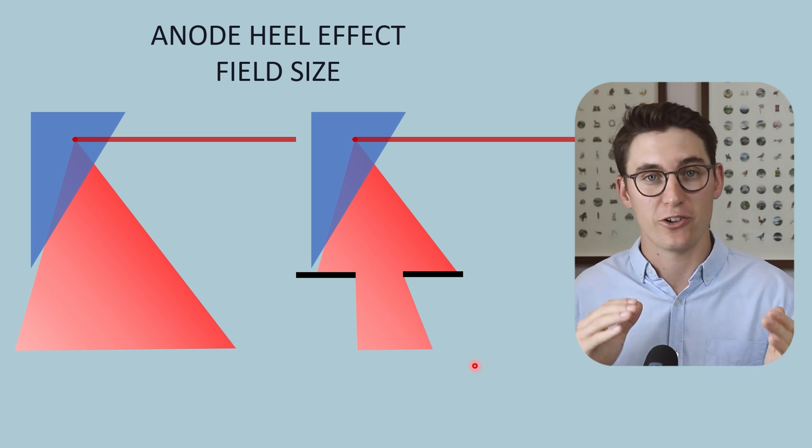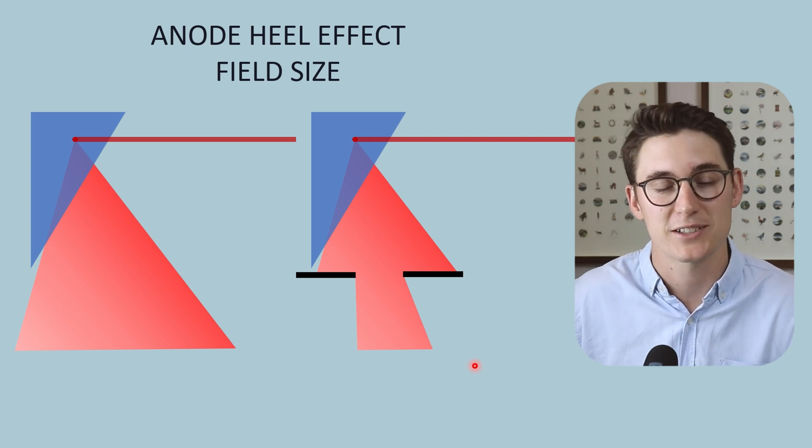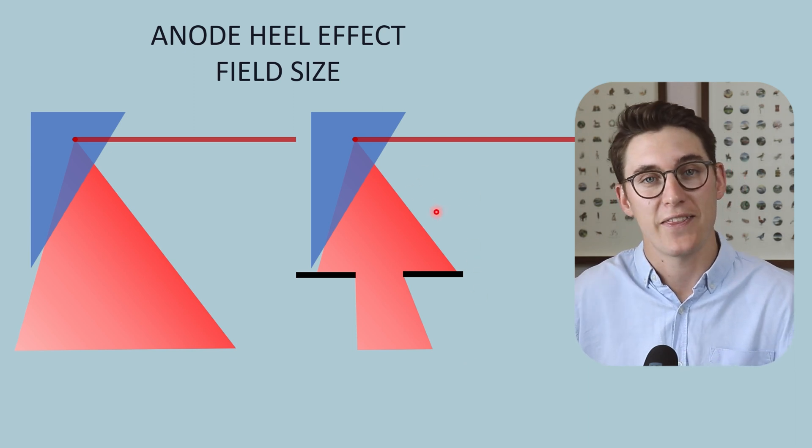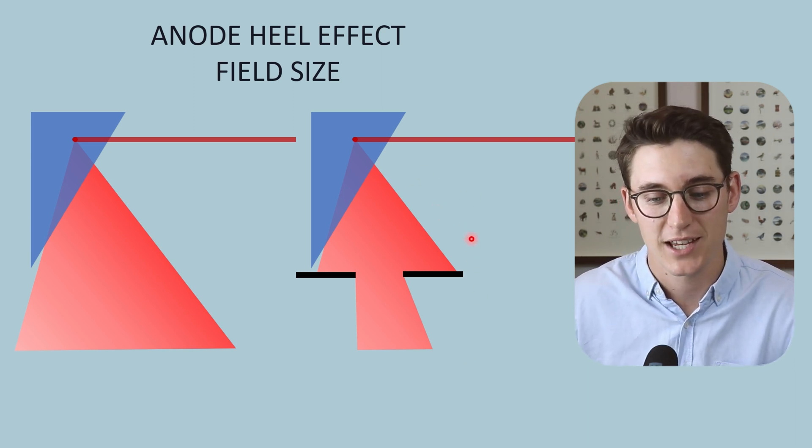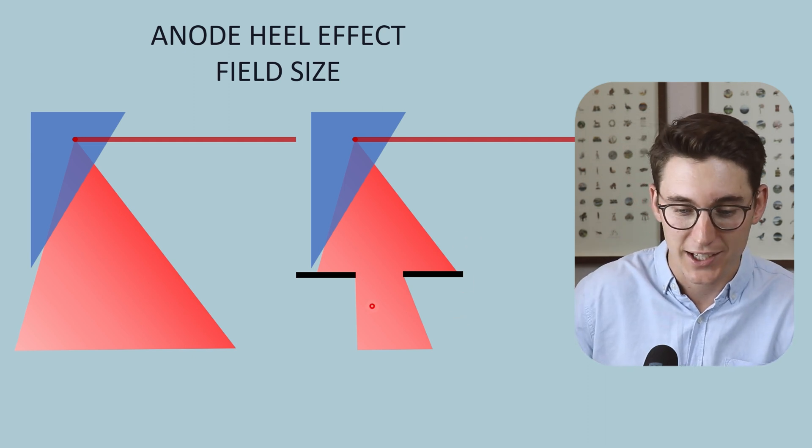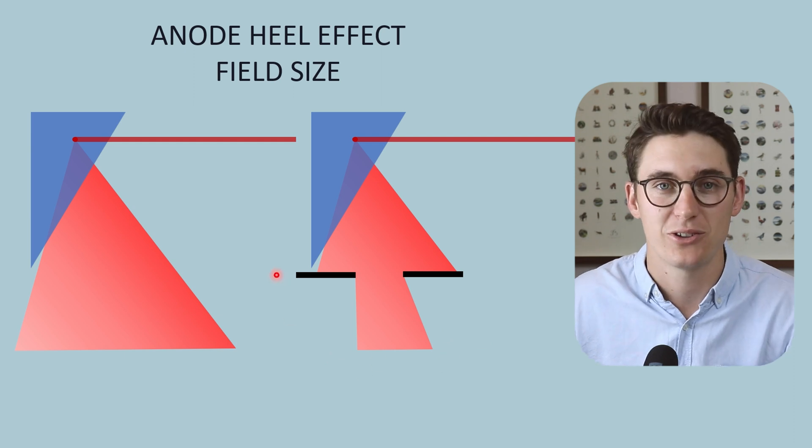So firstly, we can change our anode angle. Increasing our anode angle reduces our anode heel effect. We can move our detector further away from the source and that will reduce the anode heel effect. And we can collimate or reduce the field size that we expose our patient to and that also will reduce the anode heel effect.